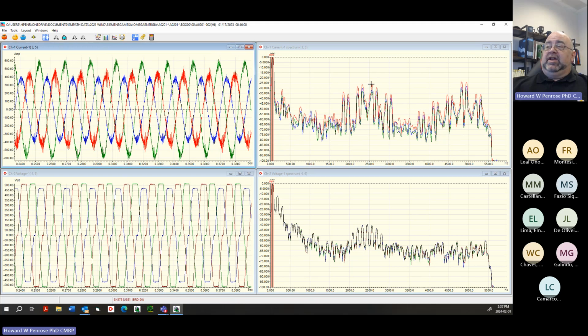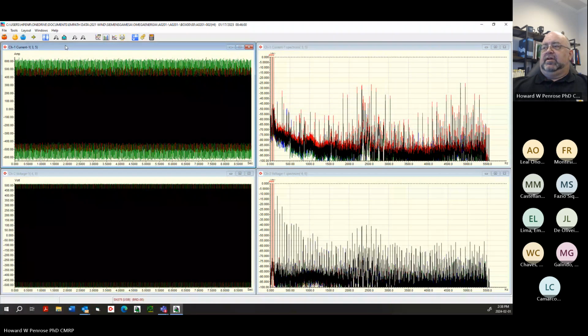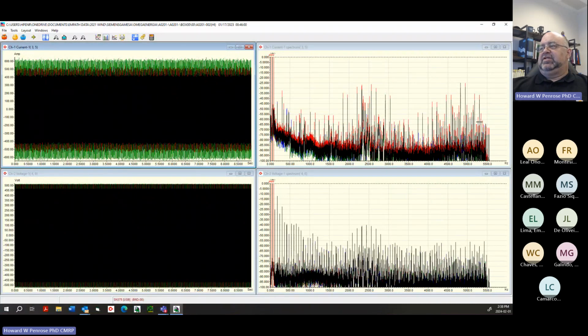And this, by the way - the center of this noise tells me the primary inverter frequency, which would be just under 2,500 hertz. So right in the center, that's that, and this is a harmonic of it. Things that relate to the transformer resonance and heating happen in between.